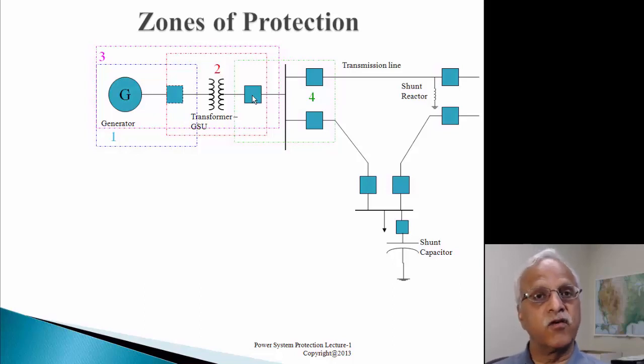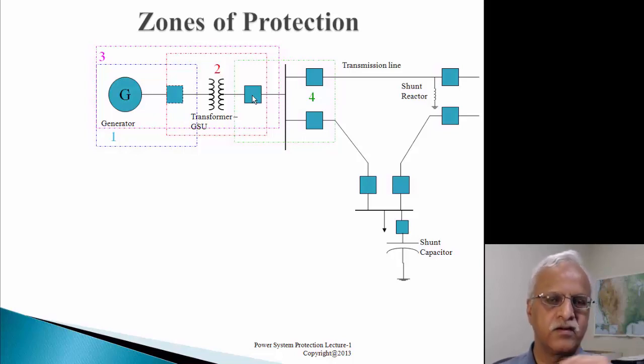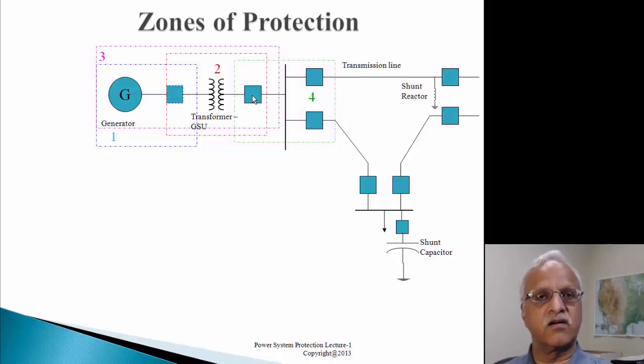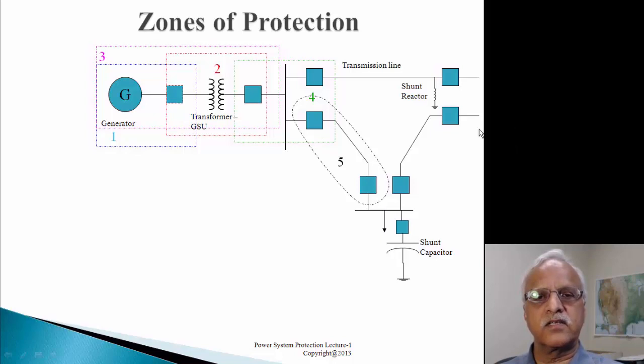Whatever current flows into the bus must equal what flows out. As you know, the sum of currents at any junction must equal zero. If there is a difference, we know there is a leakage, a fault, or another current path. We trip the bus - meaning we open all the breakers associated with that equipment. Similarly, if there is a fault on a transmission line, we open breakers at both ends of the line.